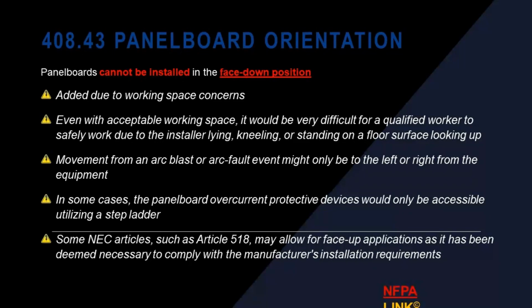Here's a code change. In addition to not being able to be installed face up, panel boards now in 2023 cannot be installed in the face down position. So 408.43. So even with acceptable working space, you cannot put a panel in the face down position.